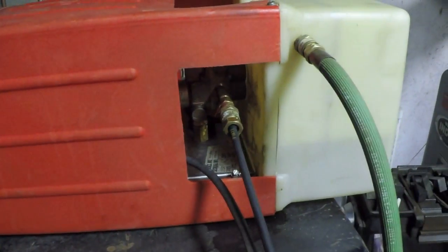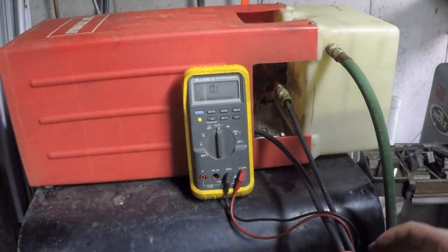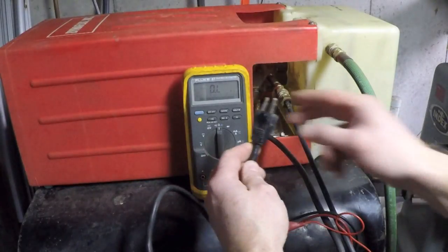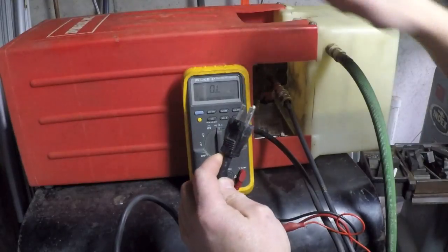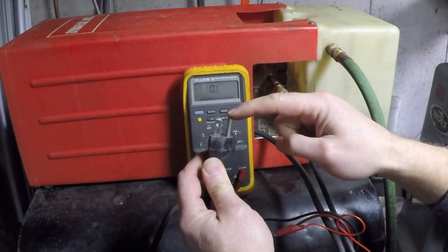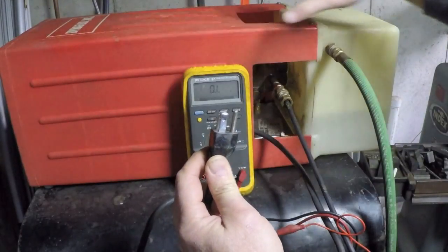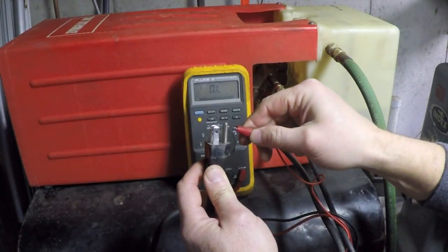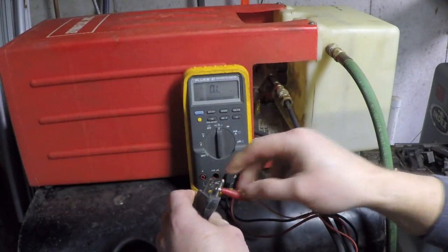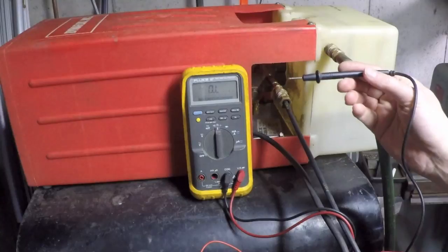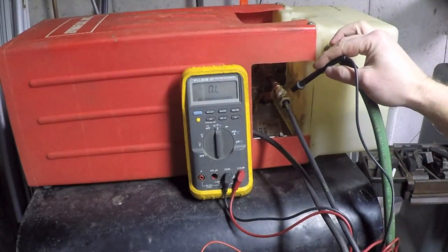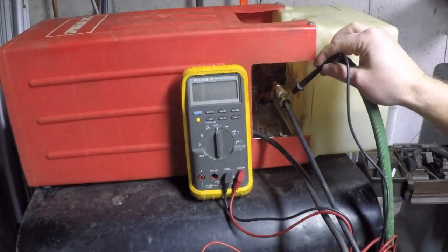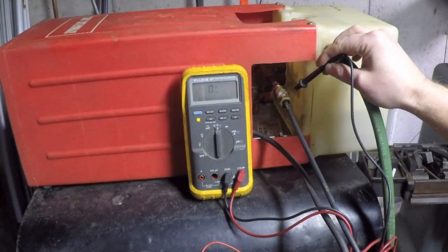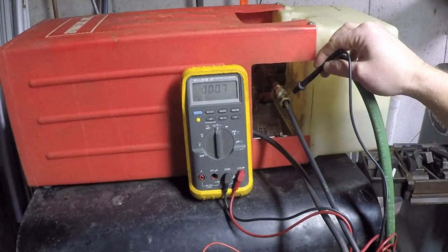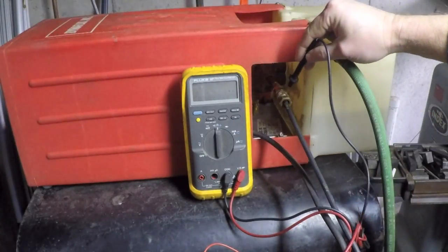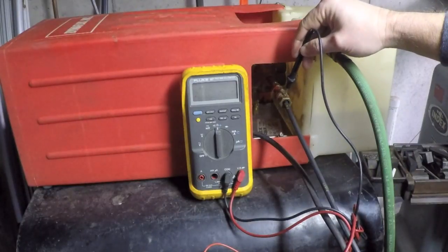So the question is, is this at ground potential? Let's do a little test. I've got my cord here for my cooler, and we've got a ground pin. This is how this unit is grounded for safety. If I connect one side of my ohm meter to the ground pin, and then touch the other probe to this brass fitting right here, I can see that I have zero or virtually no resistance, meaning the body of this pump and all the fittings are grounded.